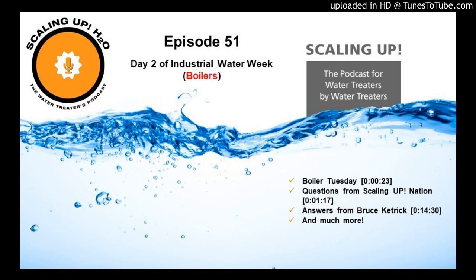With the introduction of reverse osmosis to a lot of boiler systems, due to the tremendous energy savings with reverse osmosis water, as well as the fact that it's now become economically feasible to use in boilers, that has changed the concept entirely, because with RO, your solids levels are lower, your treatment level is much lower. Hence, to remove the solids, you can reduce your blowdown. And in many cases, we're finding that 0.2 to 0.5% blowdown is more than adequate.